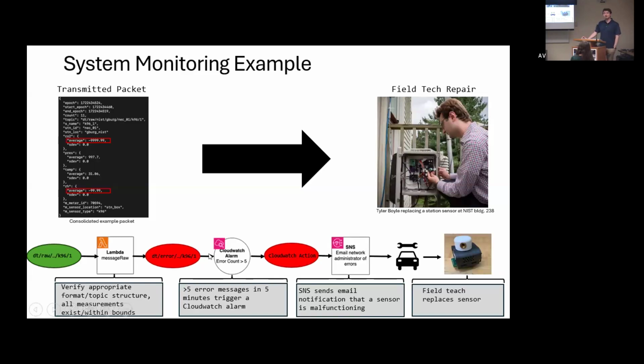From there, we have an alarm that sits there, watching. When we have 5 error messages that occur within 5 minutes, it triggers an alarm and sends an email saying sensor number 1 on box number 3 has failed. From there, I go out and replace it. So there is still a human aspect to it, but it's a way for me to detect a system issue.